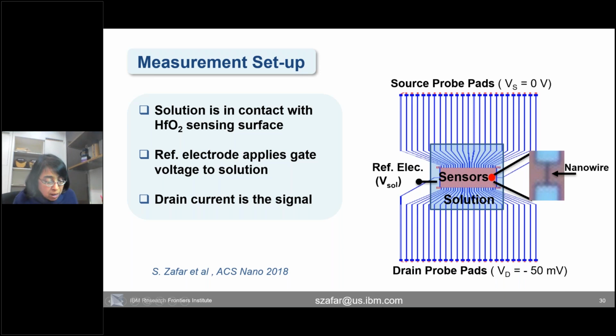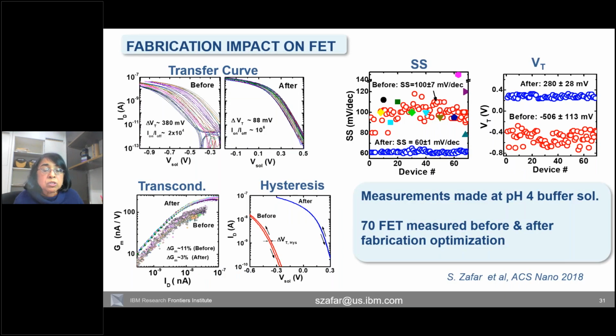And we do all this for benchmarking, for comparison; we are doing it in pH buffer. So first we wanted to see how the process has improved everything. This is the sensing signal as a function of applied voltage to the solution through the reference electrode. Here you see the sensor-to-sensor variation was huge, 380 millivolt all over. After improvement, it has gone to 88 millivolt. And we also see a huge improvement in what we call the lowest signal, the off signal, and the on signal.